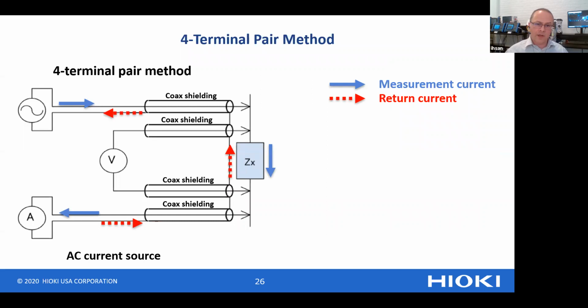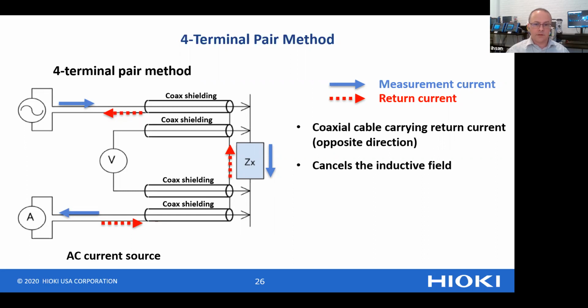One way of solving this problem is referred to as the 4-terminal pair method. The only difference here is that the force and sense lines are shielded with coax, and the measurement current is returned in the opposite direction through the coax shielding. Because it's carrying current in the opposite direction, it cancels the inductive field. And by this method, we're able to take super low impedance measurements of less than 10 milliohms using AC.